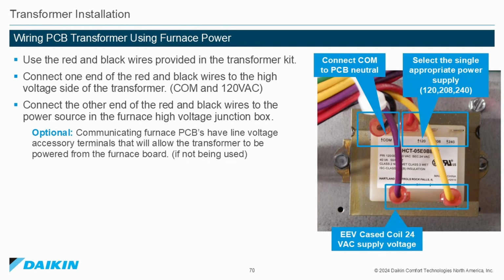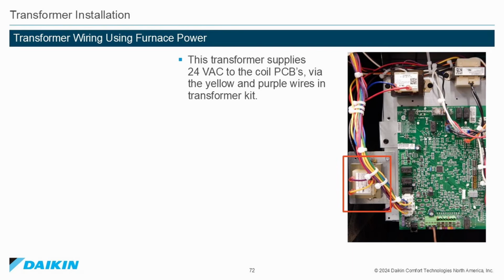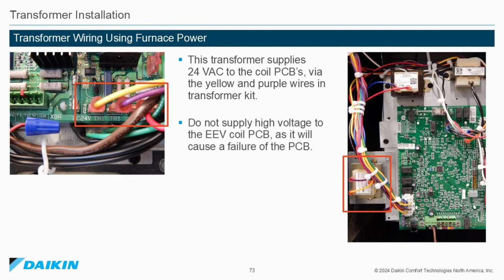Communicating furnace PC boards have line voltage accessory terminals that will allow the transformer to be powered by the furnace board if that connection is not being used. Transformer wiring using furnace power. The transformer supplies 24 volts AC to the coil printed circuit boards via the yellow and purple wires in the transformer kit. Do not supply high voltage to the EEV coil PCB. It will cause the board to fail.